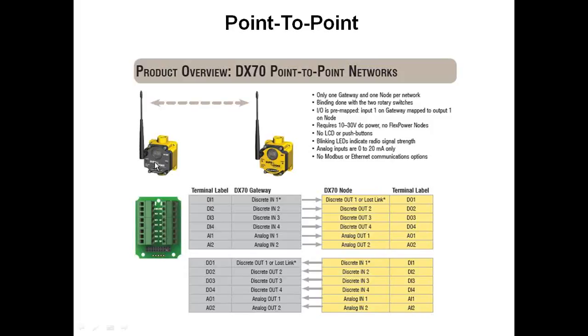This wiring chamber is actually inside the unit, and at the factory we just pre-map that. So whatever you put on input 1 here is going to turn on whatever you wired to output 1, whether that's discrete or analog. Here are some things to be aware of.